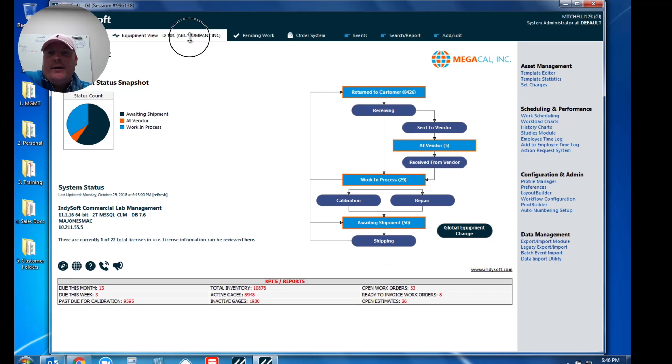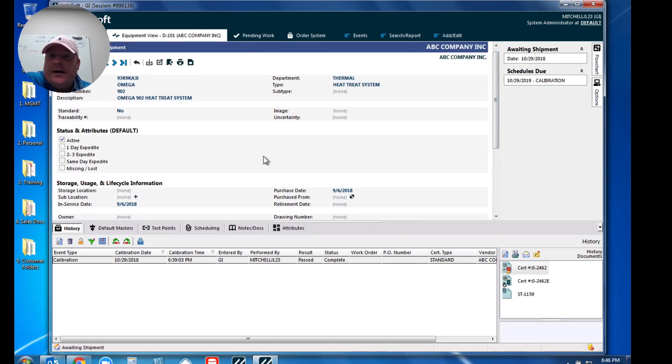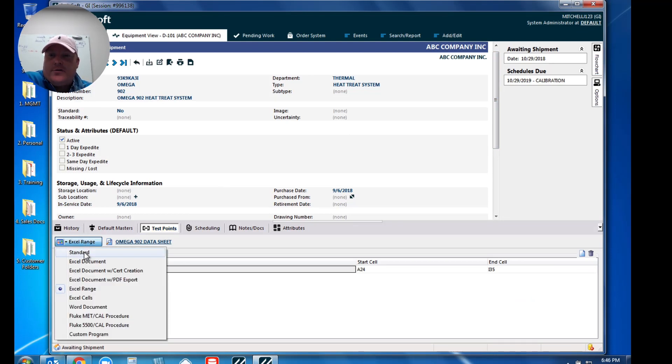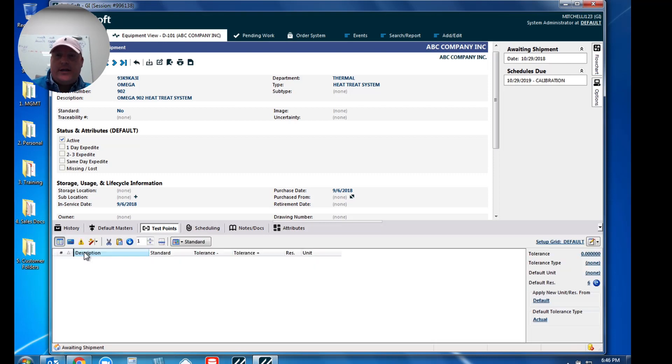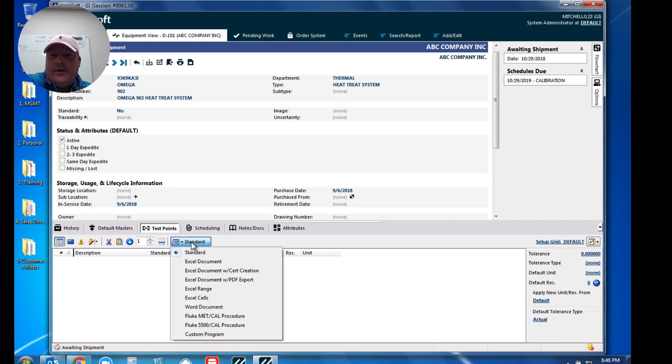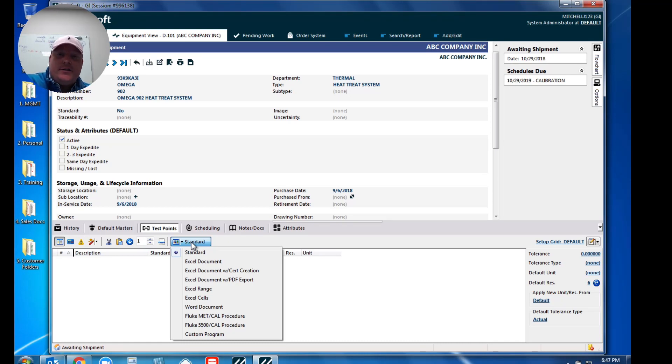The first thing that we're going to do is I've got a piece of equipment sort of already staged and set up to show you how to do this. When we go to our test points tab, a lot of you are familiar with seeing our standard test points where you would put in your upper, your lower limits, any additional columns that you may want to see presented on the certificate. But when you click on this option here, you'll notice that we have not only your standard test points but we have what's called an Excel document, an Excel document with cert creation, you've even got an Excel range, Excel cells, and a few other data collection methods.